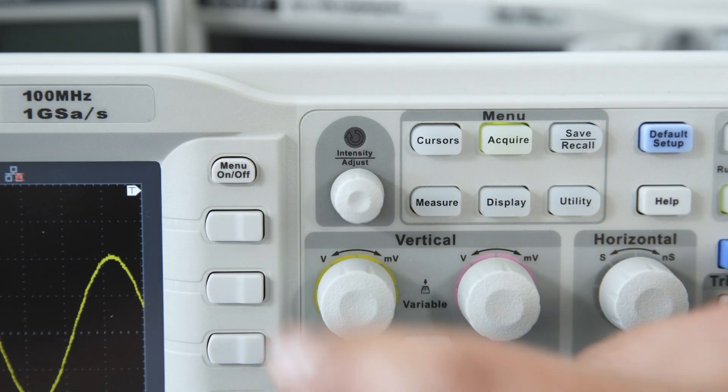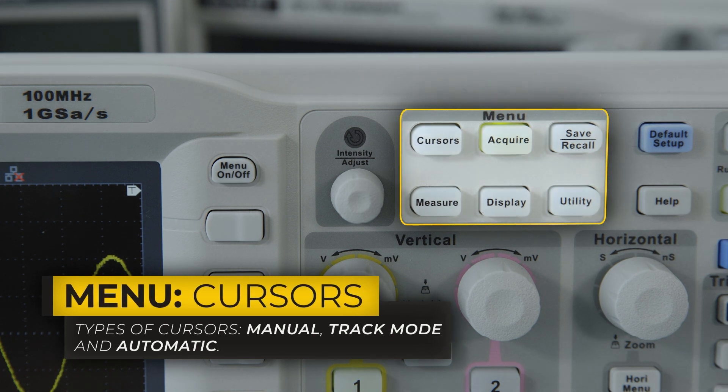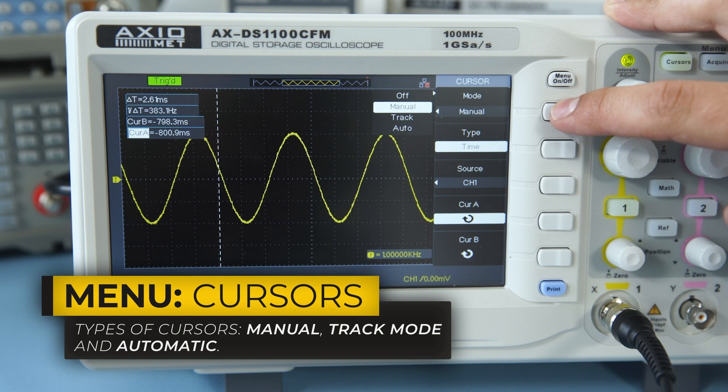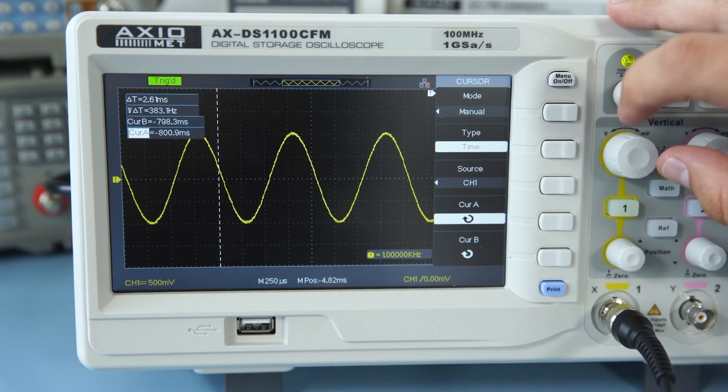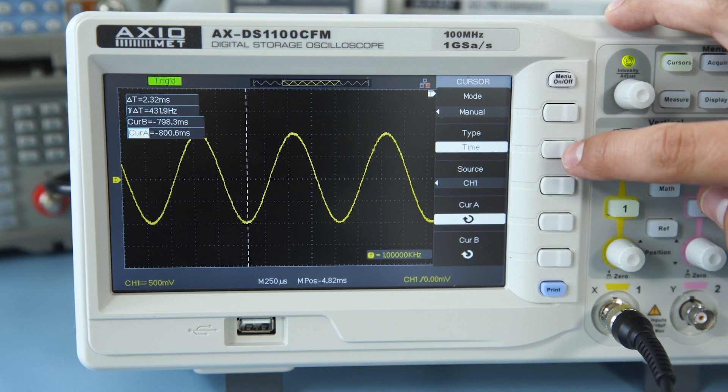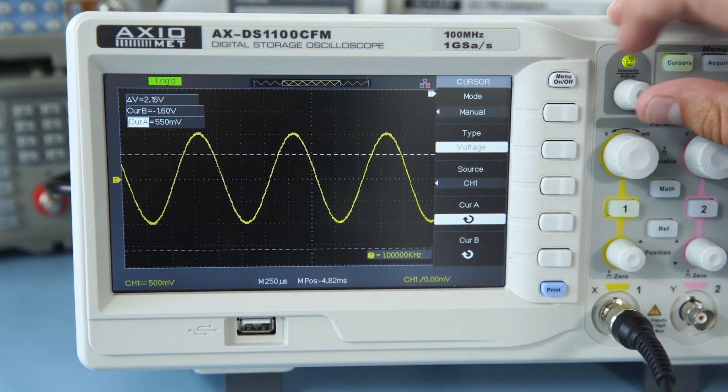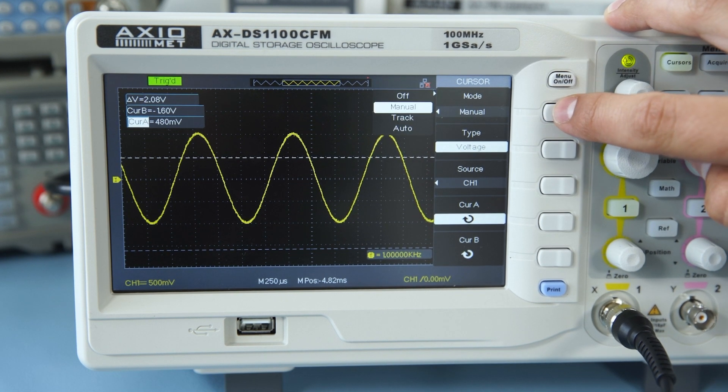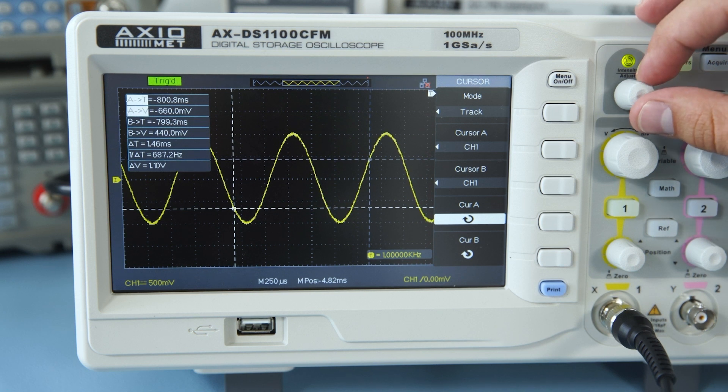After signal acquisition, we can perform some measurements. First, we will cover the Cursor menu and then the automatic measurements. There are three types of Cursors to choose from: Manual, in which the Cursors are adjusted by the user with the Universal knob, and Track mode, in which the Cursor is following the signal.